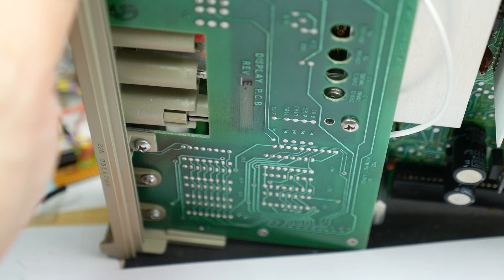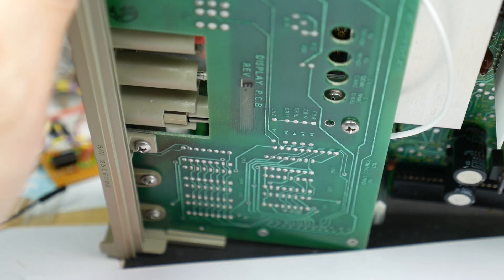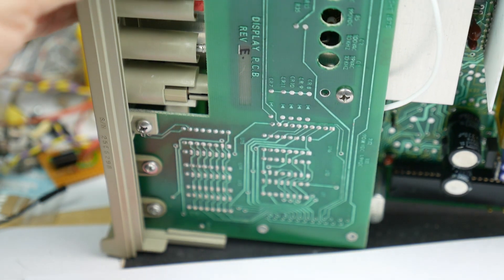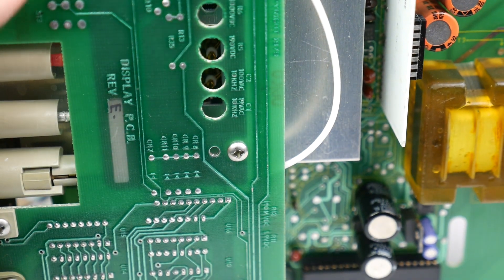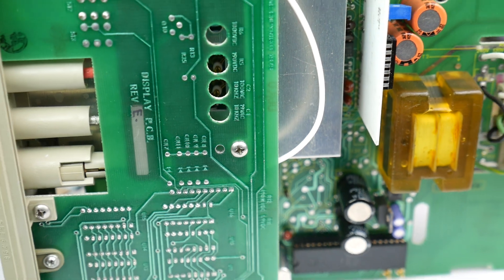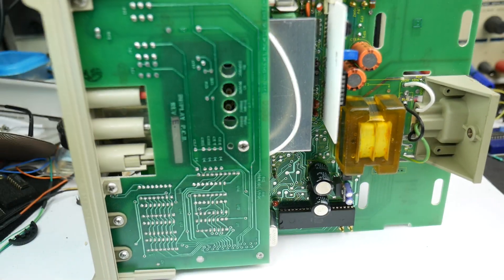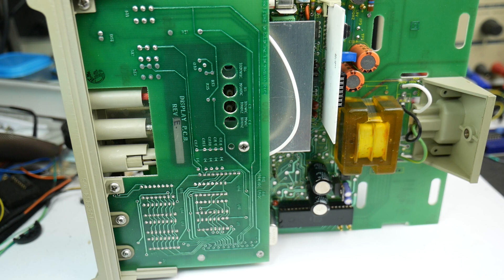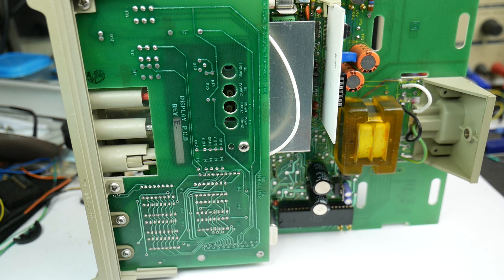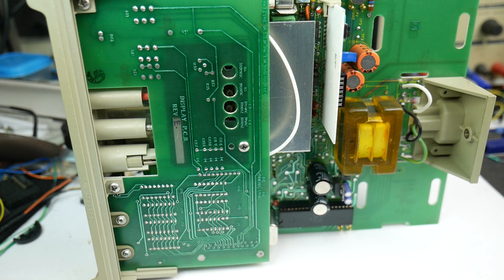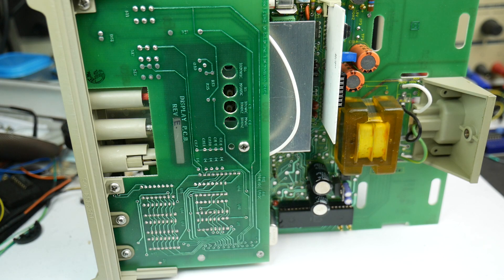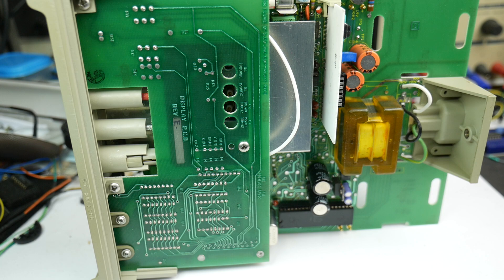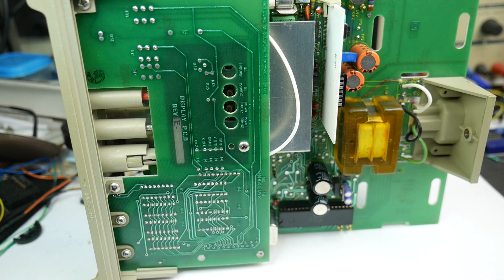It's also got the relative measurement mode, which is something I doubt I'll ever use, but at least it's there. The other thing that the 8010A, looking at it now, has got a 10 amp current range. It's got an extra terminal on the front for a 10 amp current range, which this hasn't. Maximum current for this thing is 2 amps. The 8010 has got the same internal safety fuse. It'll be a 10 amp rated thing, and it's constructed in a very similar way internally. But it, as I say, has one fewer digit in the display.